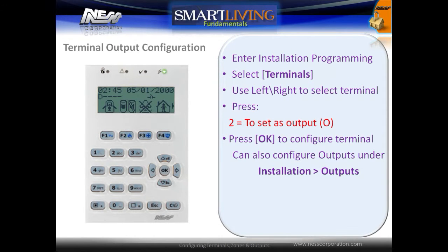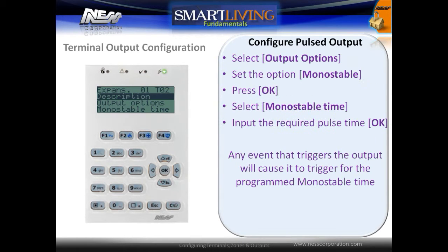To program a terminal as an output, enter into installation programming and select the Terminals menu. Use the left and right arrows to select the terminal and press the number 2 to set the terminal as an output. To configure the terminal, press OK, or configure all outputs under the Outputs menu in installation programming. To configure an output to be a timed pulsed output, select the Output Options.